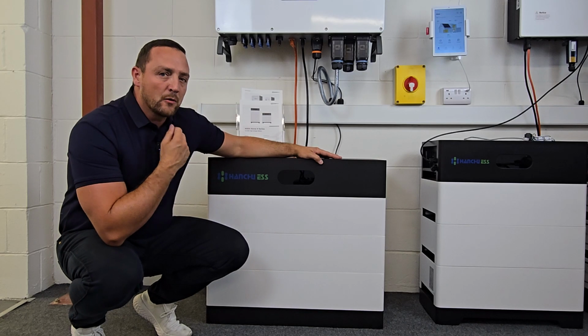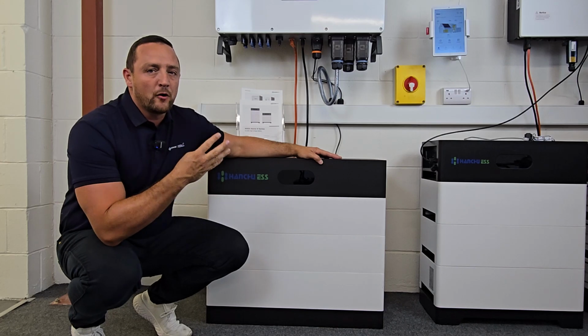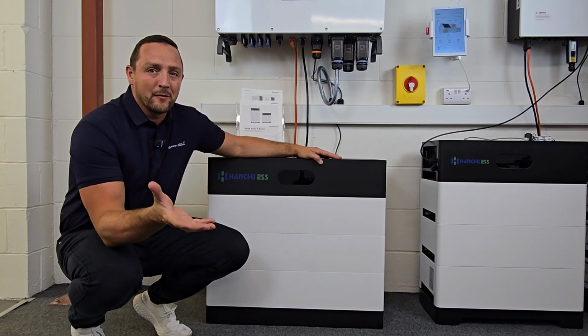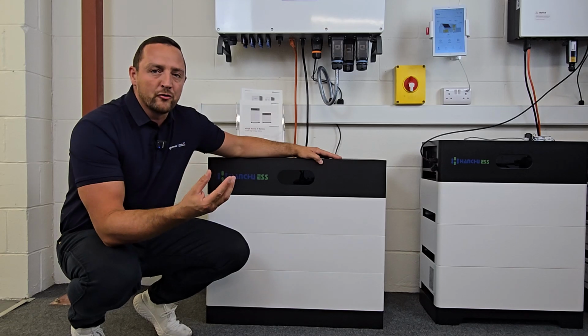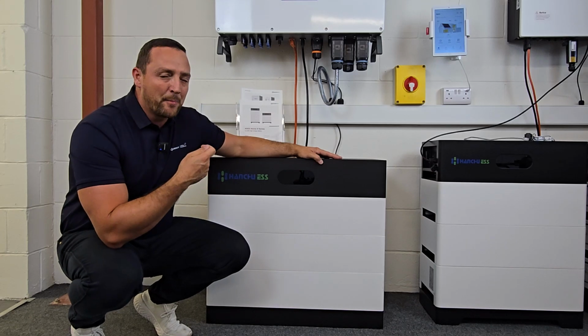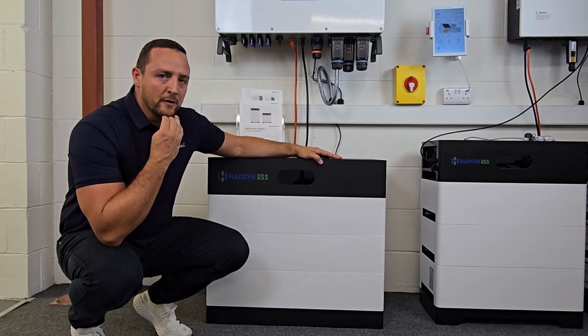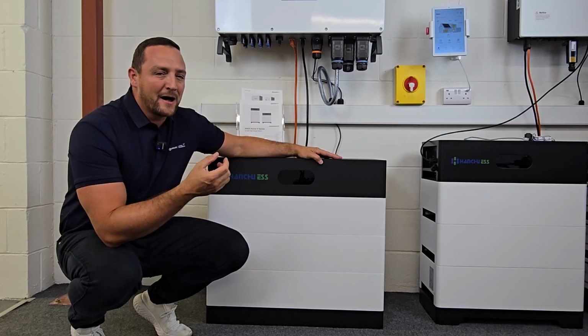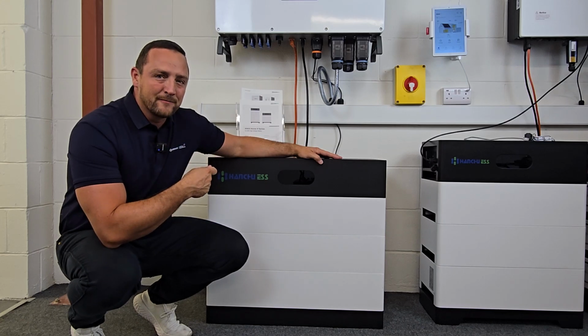And then with the 50 kilowatt C&I unit, you can actually have up to 4 stacks. So you can effectively have up to half a megawatt of battery storage per controller. And let's not forget that they are parallel as well, up to 4 controllers. So that's quite a lot of battery storage you can have with these applications.